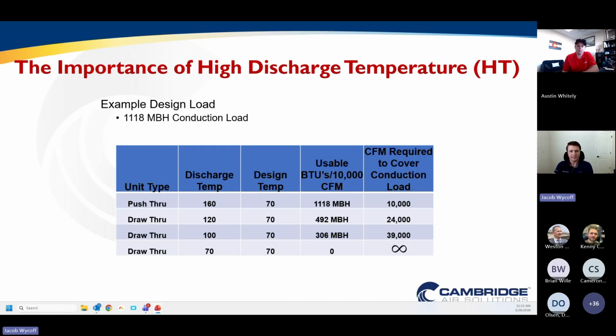So take, for example, a space that has an 1118 MBH conduction load. The conduction load being the transmission losses through the walls and roof of the space, as opposed to the air load of the space. Things like infiltration and ventilation would make up the air load. Whenever you're heating a space using 100% outside air, you need to make sure that the total heat load of the space is covered by the equipment that you provide, but also that the conduction load specifically is covered by the equipment that you provide.